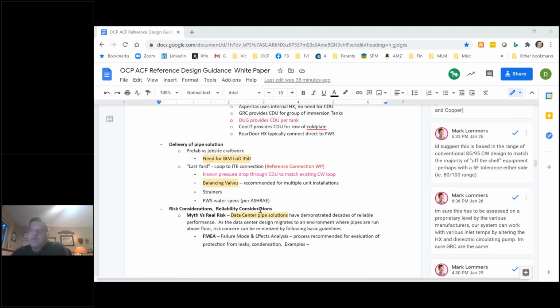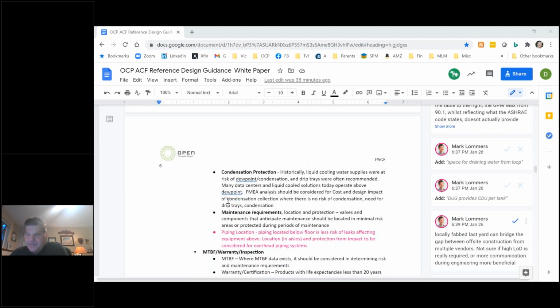One area that I'd like to take advantage of the people on the call today, there's two areas. One is that we had this discussion on dew point. And I think I saw Jason on the call. The key concern I have with dew point is that condensation is one of the nefarious aspects of liquid pipes in data centers. Not that condensation anywhere isn't bad, but pipes, generally because of their cold nature, can often operate below dew point for the given humidity of a data center. And why is that bad? Well, I don't want to scare you with videos and pictures, but if you ever search the internet for images of corrosion under insulation, you'll see that it can happen even when you've insulated your pipe: if you break your vapor barrier, it will corrode.